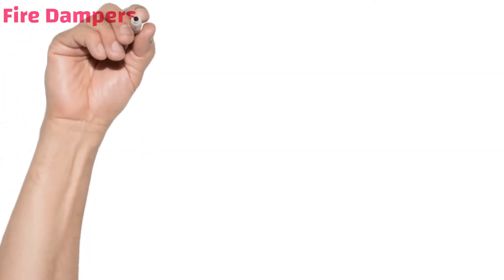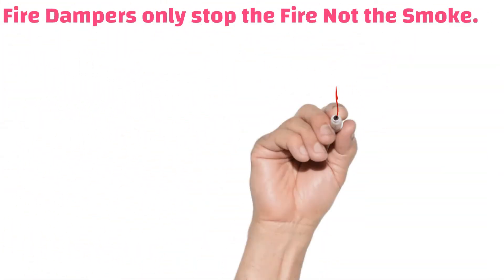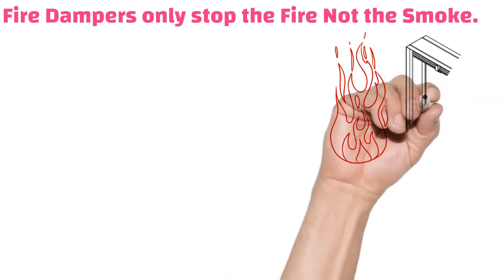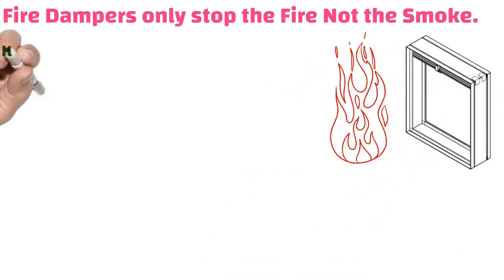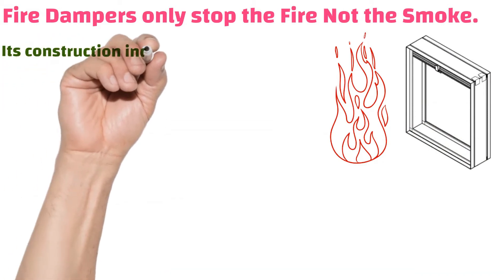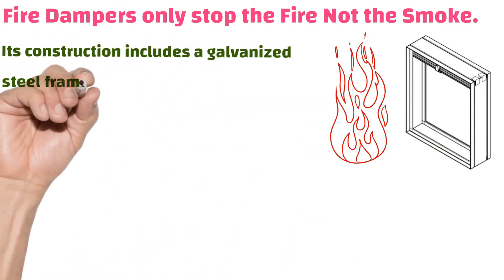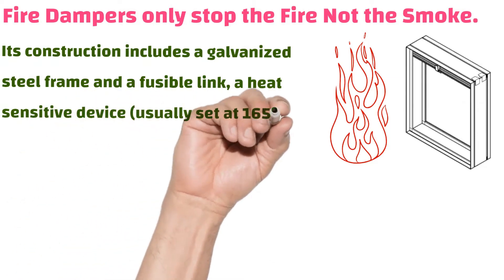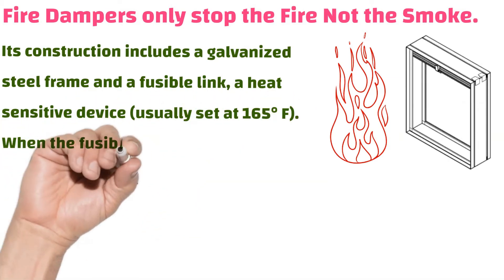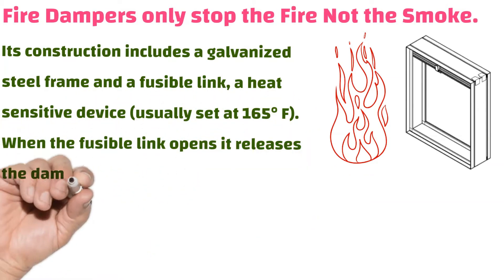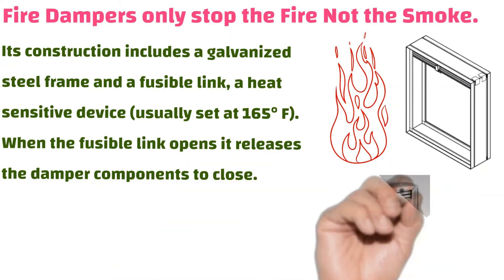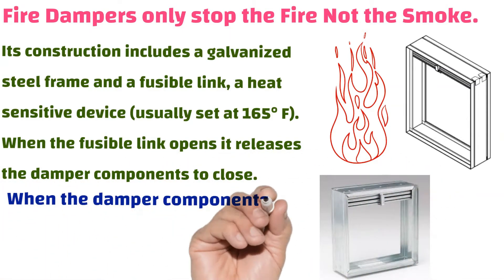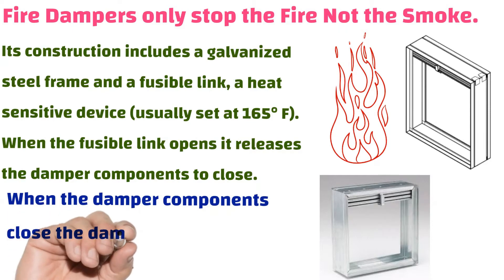Remember, fire dampers only stop the fire, not the smoke. Its construction includes a galvanized steel frame and a fusible link — a heat-sensitive device usually set at 165 degrees Fahrenheit. When the fusible link opens, it releases the damper components to close, restricting the migration of fire.